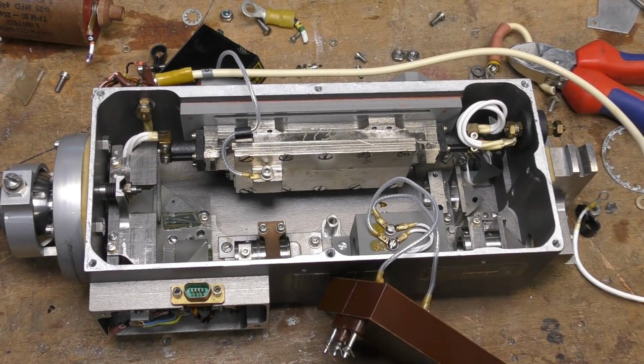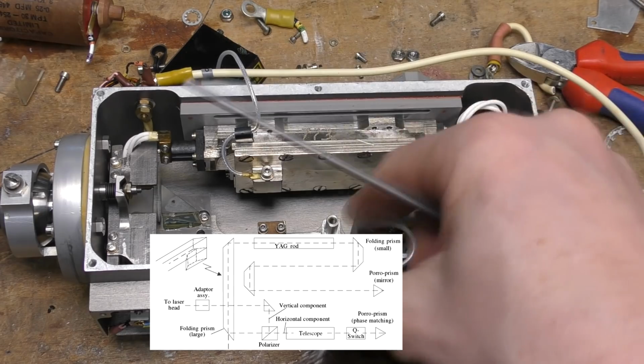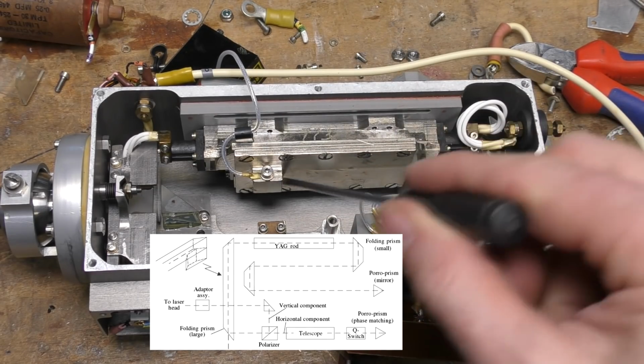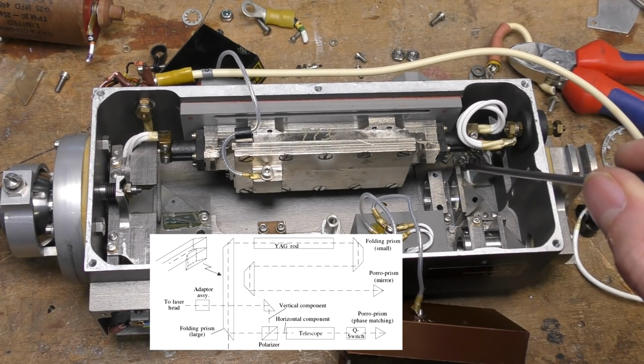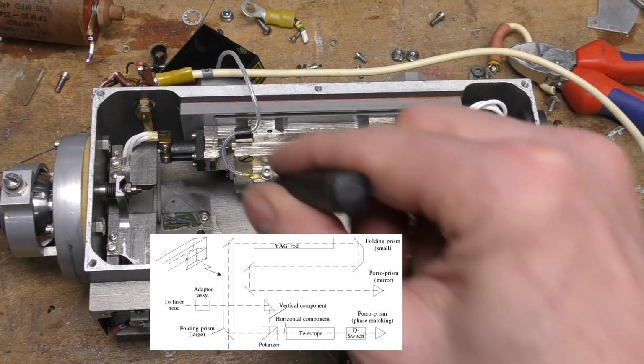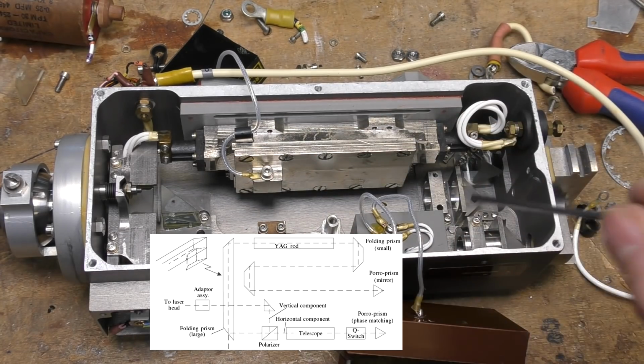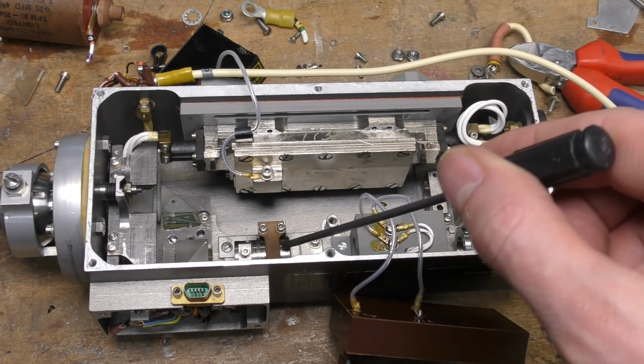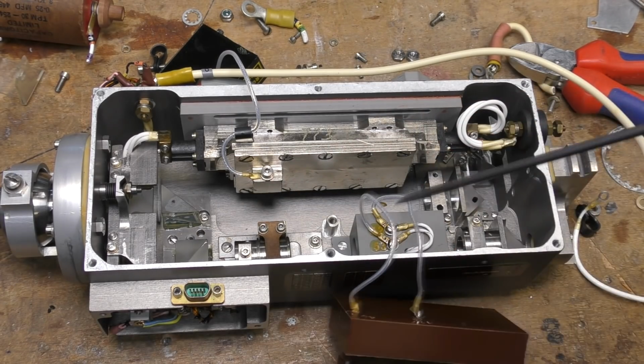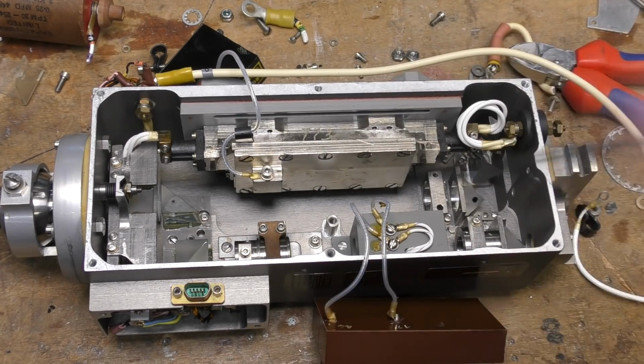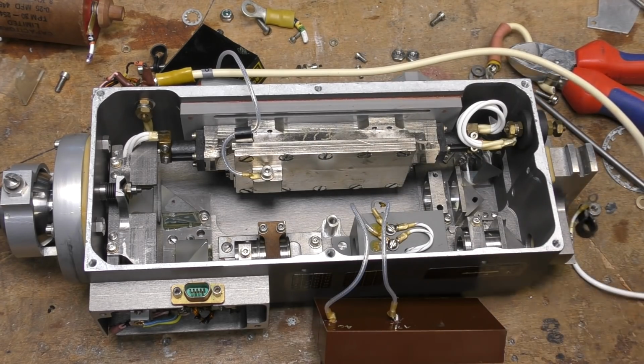The beam takes about 4 passes through this cavity, obviously just to reduce the size. There are various prisms in here, so it goes through the rod, is reflected down this prism in the corner, reflected back into this prism, then back, then across through some optics, through the Q-switch, and then back, and it's reflected back through this prism. So all the optics have been folded down to make this a very compact unit.